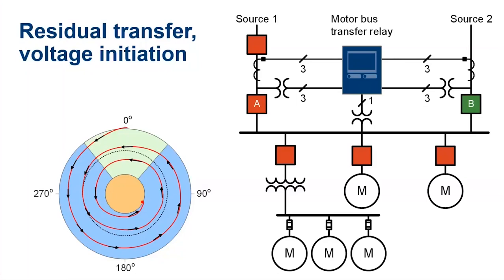So we have an independent algorithm to track the frequency in such a way that we can measure the magnitude as the voltage goes down and the voltage and frequency go. When we detect that the voltage goes below the threshold, we can just issue a close, or we can start a timer and issue a close.